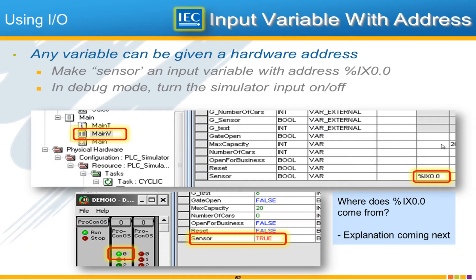Input 0 is already configured in the system as address %IX0.0. All you have to do to make the tie between a physical input and a variable is give it an address in the address column. So we can do that with our input called sensor — give it an address in the address column — and then we'll be able to turn that sensor on and off with the physical input. We'll explain later why IX0.0 and where that letter X comes from.